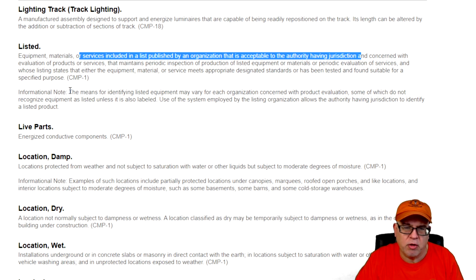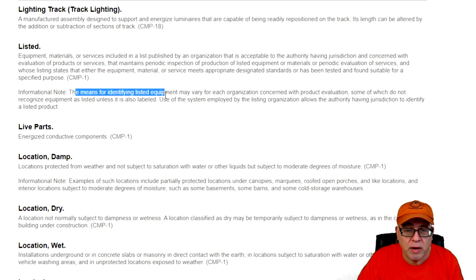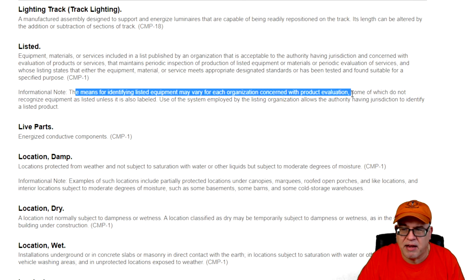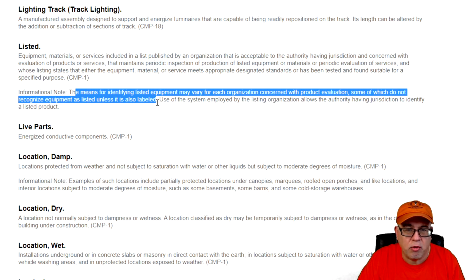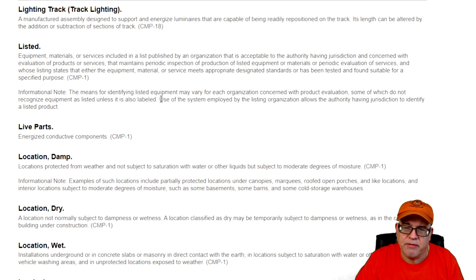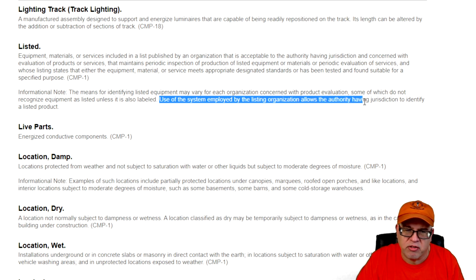So here you see an informational note that gives you a good understanding. It says, the means for identifying listed equipment may vary for each organization concerned with product evaluation, some of which do not recognize equipment as listed unless it is also labeled. So many organizations, AHJs, different things, will say, look, I'm not going to recognize this as being listed unless I see a label on it, okay? Again, some may vary. It says, use of a system employed by a listing organization allows the authority having jurisdiction to identify a listed product.